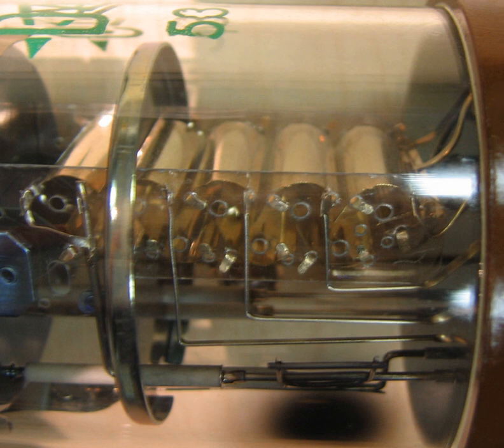Photomultiplier tubes typically utilize 1,000 to 2,000 volts to accelerate electrons within the chain of dynodes. See figure near top of article. The most negative voltage is connected to the cathode, and the most positive voltage is connected to the anode. Negative high-voltage supplies with the positive terminal grounded are often preferred, because this configuration enables the photocurrent to be measured at the low-voltage side of the circuit for amplification by subsequent electronic circuits operating at low-voltage. However, with the photocathode at high-voltage, leakage currents sometimes result in unwanted dark-current pulses that may affect the operation. Voltages are distributed to the dynodes by a resistive voltage divider, although variations such as active designs with transistors or diodes are possible.